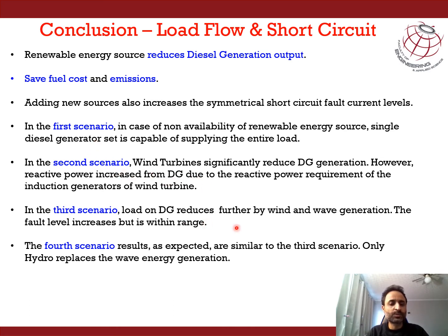In the third scenario, we indicated that the load on the DG set could be further reduced by having wave energy generation in addition to the wind generation. Of course, now there are three generation sources, therefore the fault levels have increased, but they are within the limits. The fourth scenario is similar to the third scenario, only with the wave energy generation now being replaced by hydro generation.